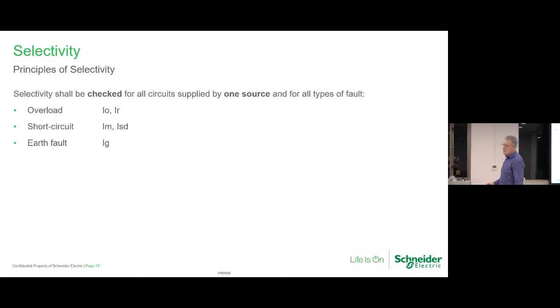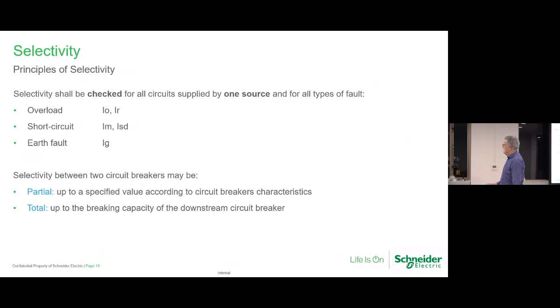Those are the three faults that we're looking to do something with. The term we use for two breakers is partial discrimination, where we can get up to a value. As suppliers, we have tables that will tell you that if we don't have total, we'll have a discrimination value up to something. You'll see that in the software tools as well. Often that up-to level is pretty low, and you just think, wow, that's not very good.